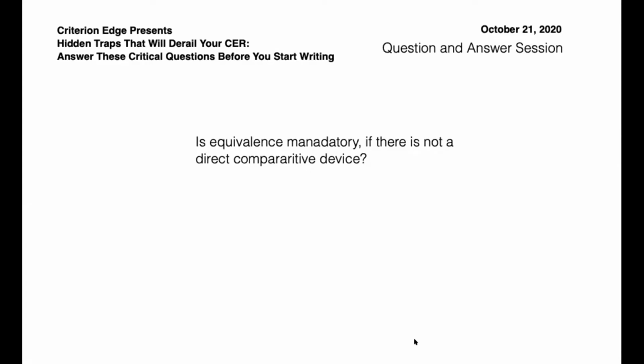Equivalence is mandatory when and if you judge that there is not sufficient clinical evidence to establish the safety and performance of your subject device. It's no more complicated than that, really. If you do an honest assessment early on of your clinical data sources for your subject device, and you deem those data insufficient to establish both safety and performance as intended, then you must consider establishing equivalence with a device that does have sufficient data to establish safety and performance.